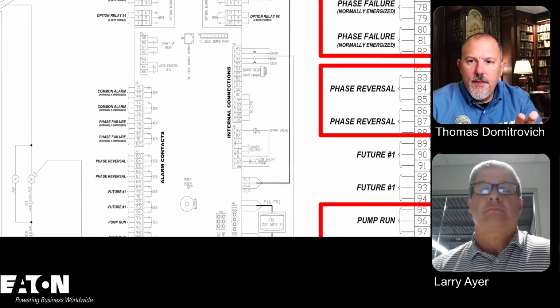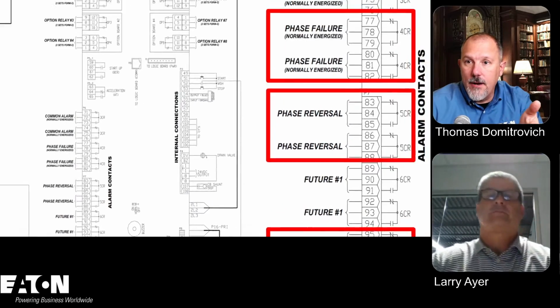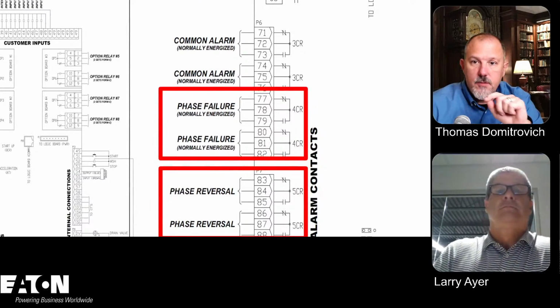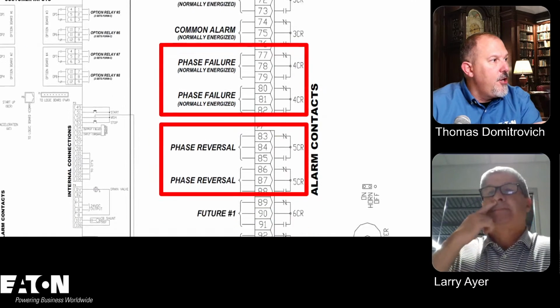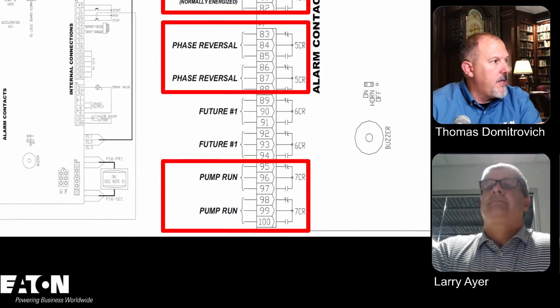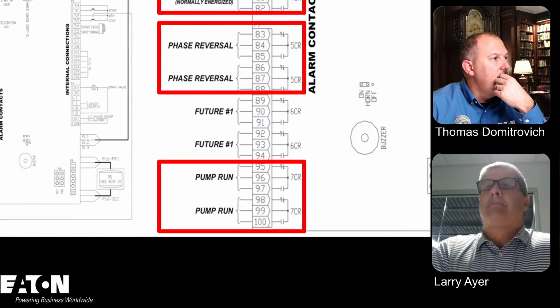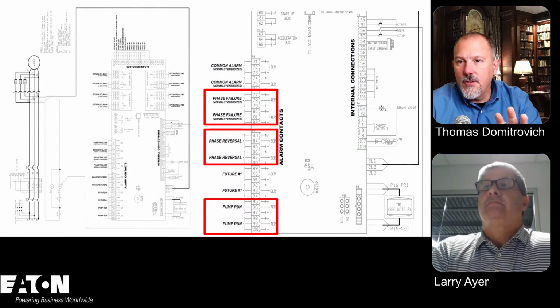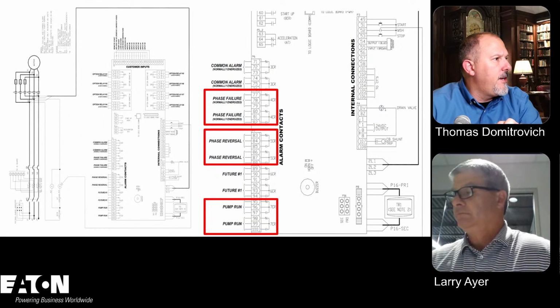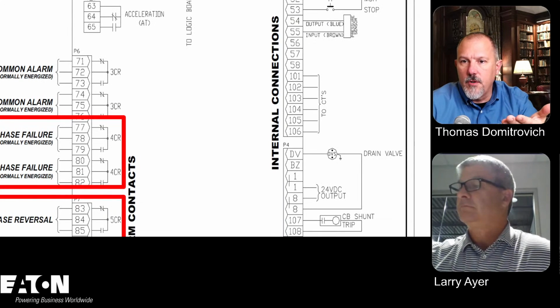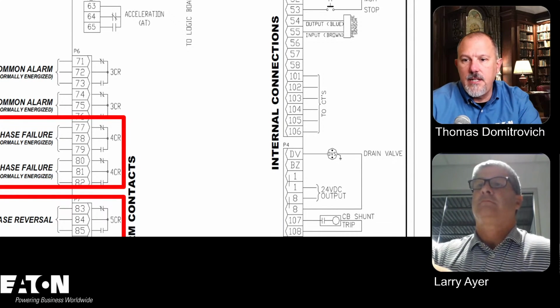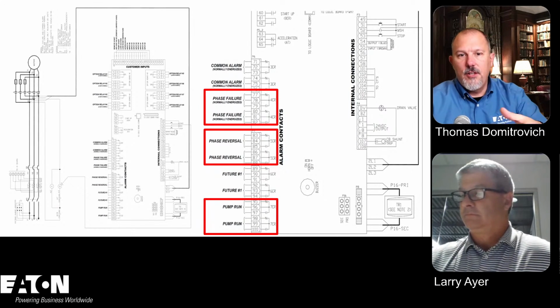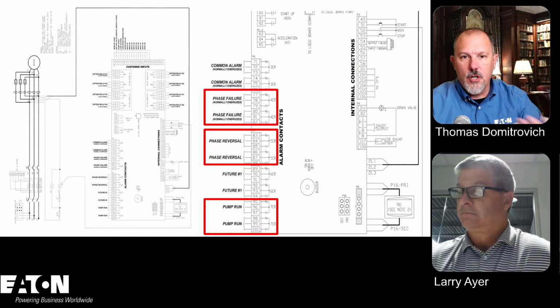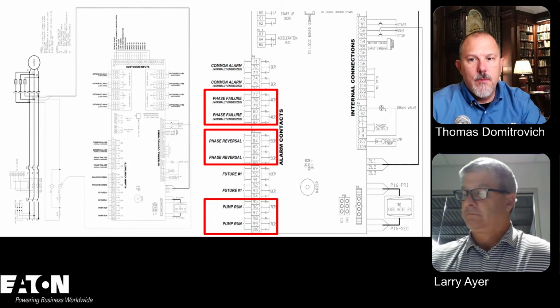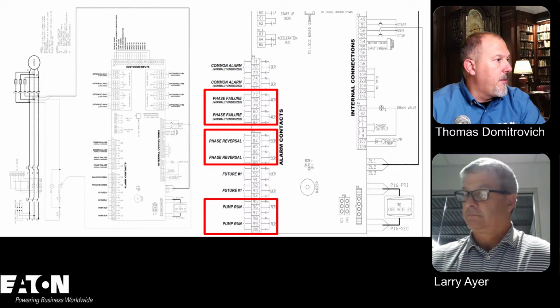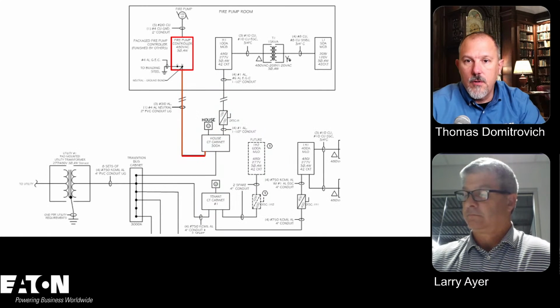But over on this side, on the board where you land all of your wiring, you'll see you have your phase failure alarms, which is required. You have your phase reversal, which is also part of the requirement. And then you have your pump run, which tells you whether it's on or off, right? Over here you'll see where it says to the current transformers. So you'll see where you land your CTs to get all of the information. That's how I'm determining whether or not that motor's running. I'm looking at current and things of that nature. And you have any of your inputs on this board that are field wired from the pump itself to the controller.